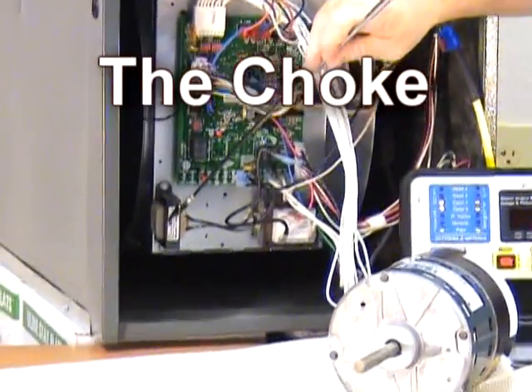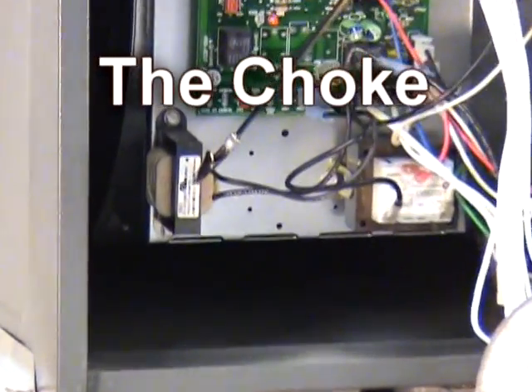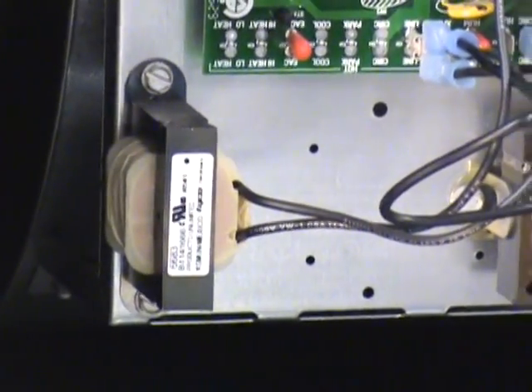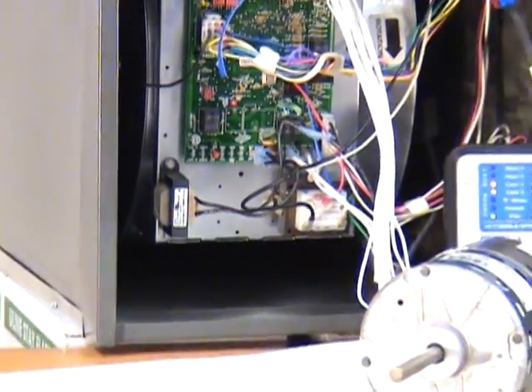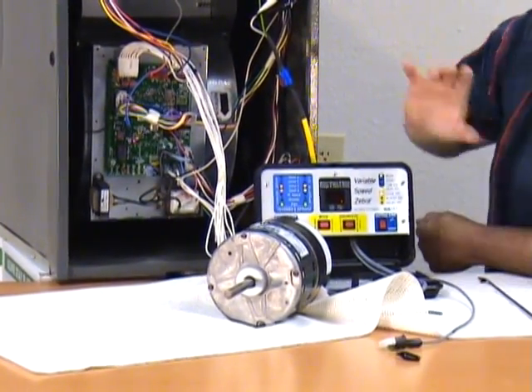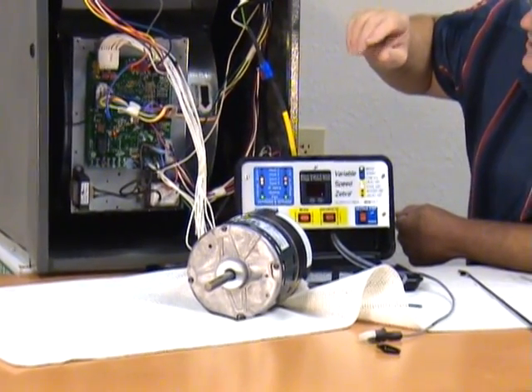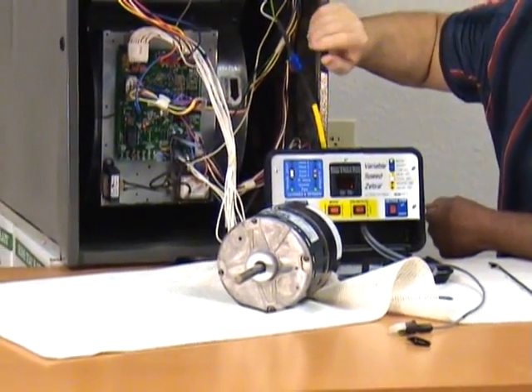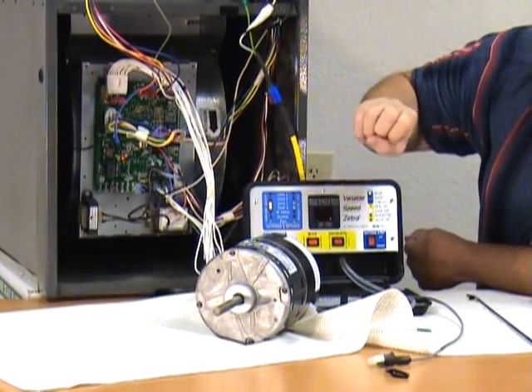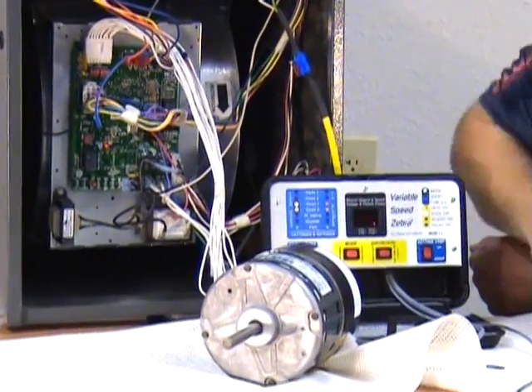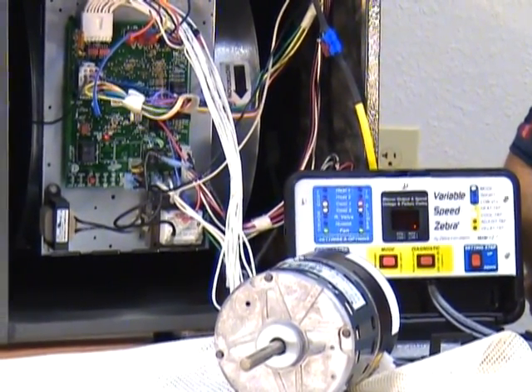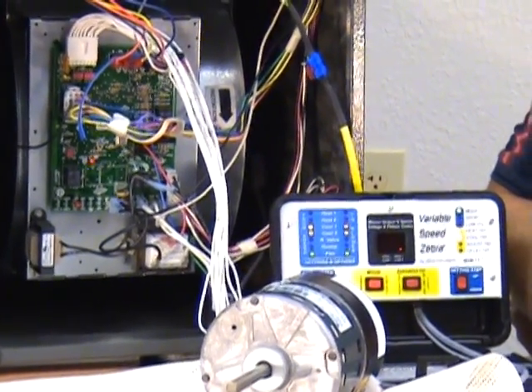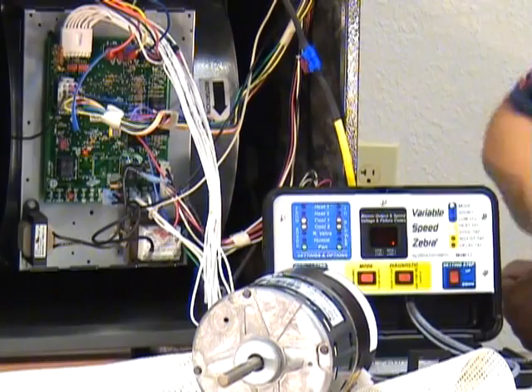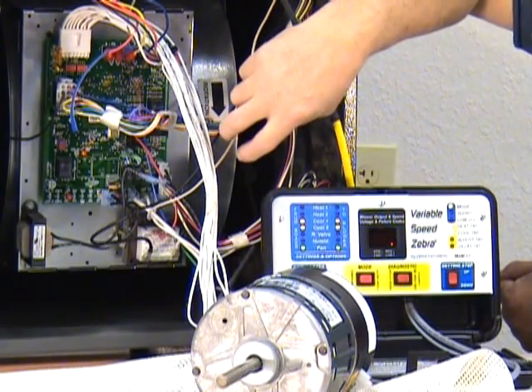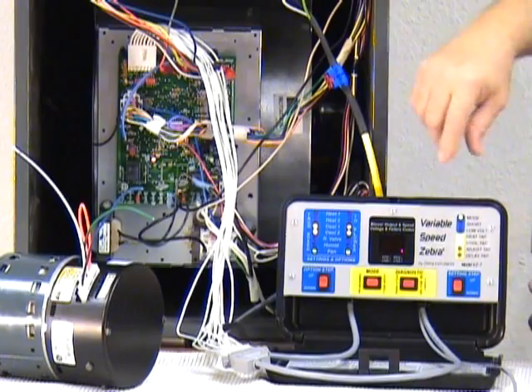There's a little device that looks a lot like the system transformer. It's actually called a choke. It only has two wires going in. It's usually one of the hot wires coming to the motor from the power supply. And it's a filter to help filter out unwanted harmonics, or spurious voltages that your system might be generating. It's to keep them from affecting the motor and to keep the motor's spikes from affecting everything else in your house. Occasionally those things will burn out if the motor has put too much of a load on it or for whatever reason. So if you're not getting 110 or 240 and you are getting it on the board, check that item. Remember, we're in the observe mode.